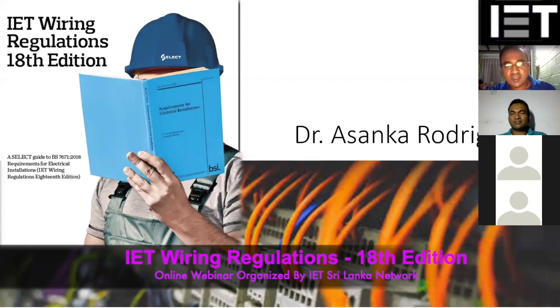Thank you. And next question, what is the allowable length of the earth wire from SPD and the size of the earth wire? Yeah, sizes also, there is a guideline. I haven't shown it due to the time limitation. For example, for the class 1 SPD, you have to use 16 millimeter squared, class 2 6 millimeter squared, class 3 1.5 millimeter squared. Those are the minimum requirement for the SPD earthing wire connection.